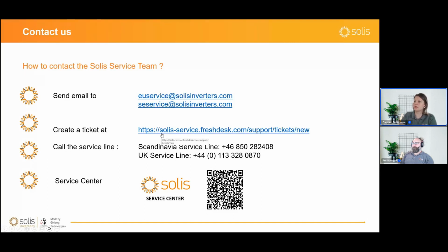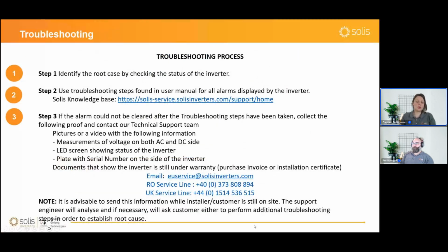And you can get in contact with us either through the email. You can create a ticket, or you can even call the service line or access our Solis service center. And if you do encounter any issues, you should let us know. Always, if you're an installer and you're doing a troubleshooting process, I would advise you to get in contact with us while you're still on site, or if that's not possible, just to gather all those informations that you think might be needed, for example, to prove a fault of an inverter. For example, measurements on AC side or DC side, LED status and serial numbers, and send these informations of the inverter to our service line, on our service email.